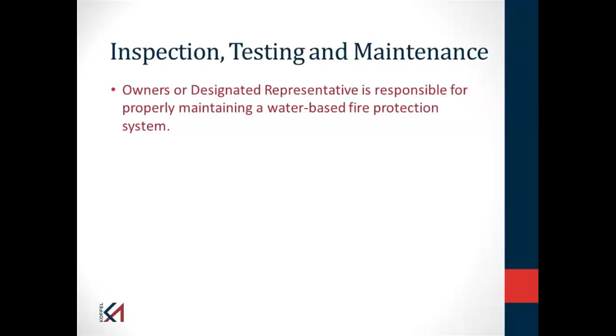Remember that essentially every one of these standards—this comes out of NFPA 25, but essentially all of the NFPA standards—puts the responsibility for inspection, testing, and maintenance squarely on the owner. You have the ability to designate that task to somebody under a contract, but ultimately you are responsible for inspection, testing, and maintenance of the system.